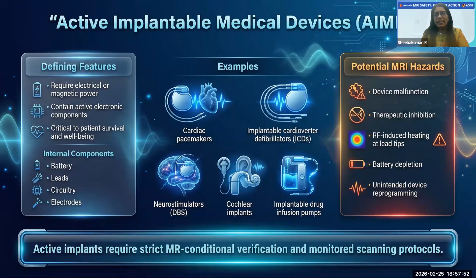An implant can have many interactions in an MR environment. The static magnetic field attracts these implants with a strong force. We call it the attractive force. If the implant is elongated and ferromagnetic, the north-south pole of the device tries to align with the magnetic field. That is the torque force. The gradient magnetic field can cause tissue heating, induced electric current and vibration, which the gradient switching can produce. And with the RF, the important concern is heating.